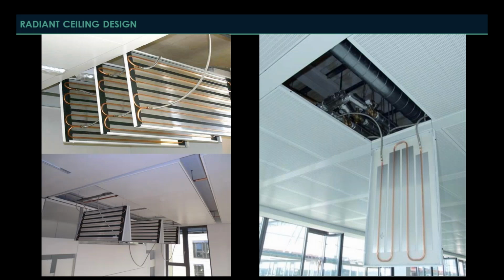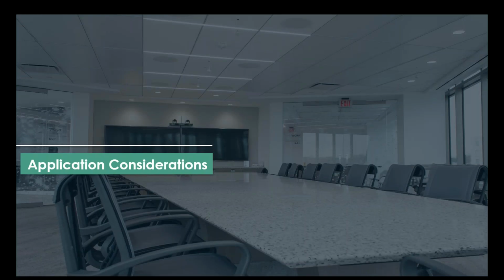Another important aspect of radiant ceilings is access. If you're going to cover so much of the ceiling with these radiant panels, you need to be able to get above it. So it's very important when you're designing these that you have access in mind. Most radiant ceiling panels can have a hinged access system where you're able to fold down the panel. And this can be done without turning the system off, without draining anything down. And that's done with these silver flexible connections to each radiant panel. Those flexible connections allow it to be opened and closed without breaking these connections.